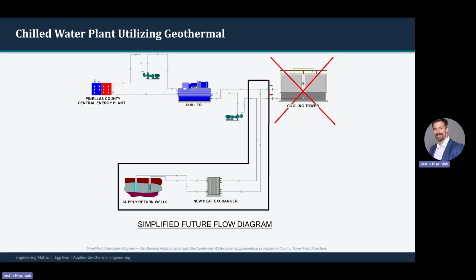A chilled water plant utilizing geothermal. This facility was originally designed with cooling towers. However, during construction, the design team made a change to geothermal. As you can see, the geothermal wells and heat exchangers replace the cooling tower. There is no water consumption for this cooling method. All of the water is returned to the ground.